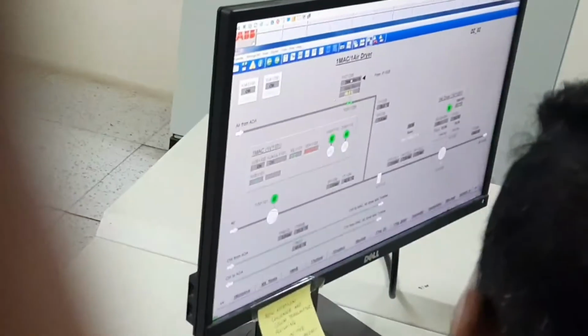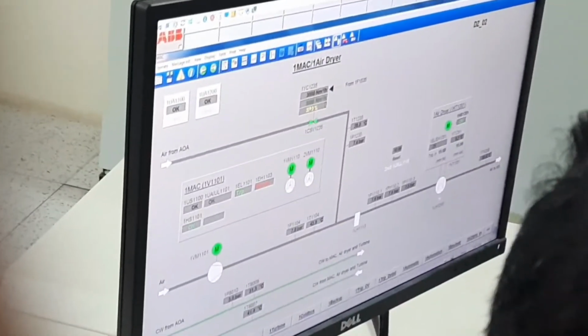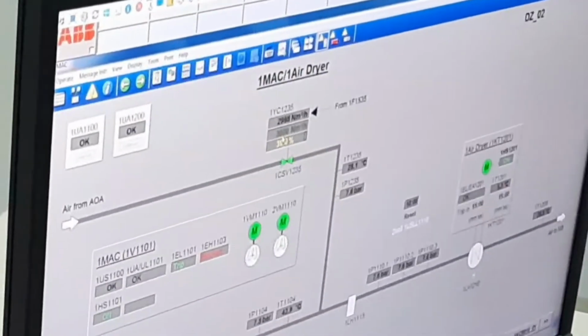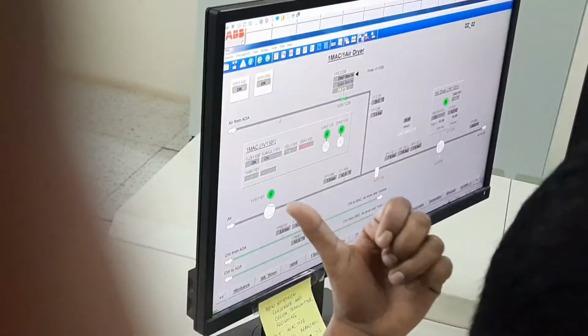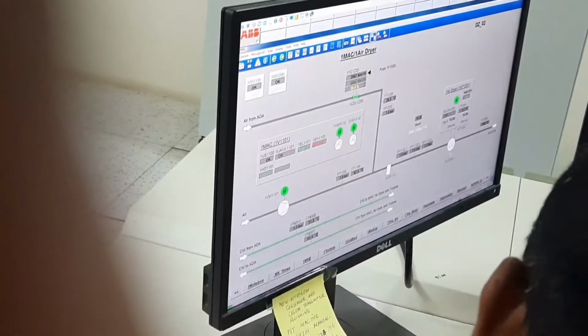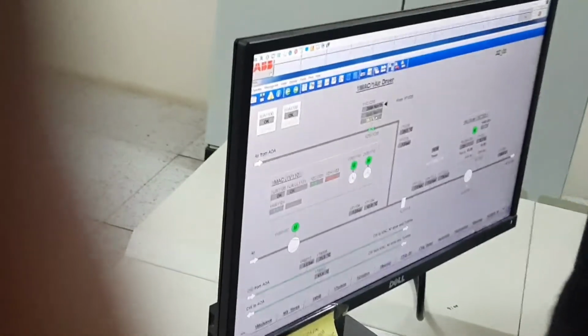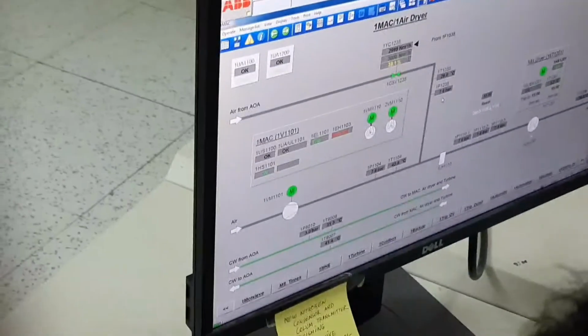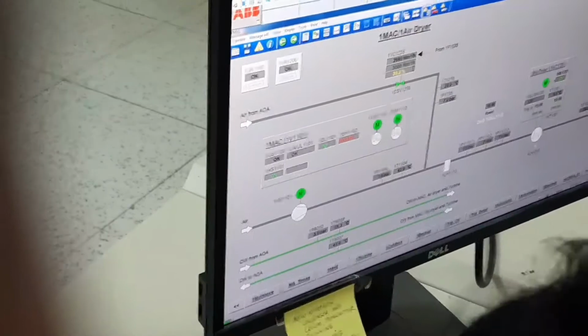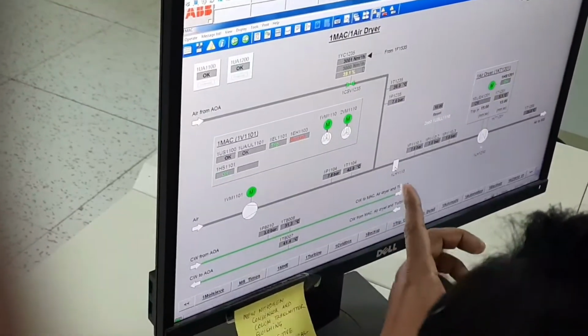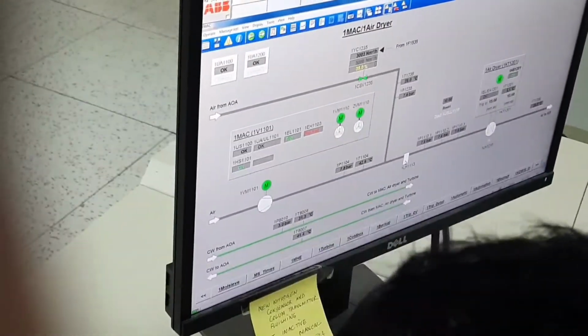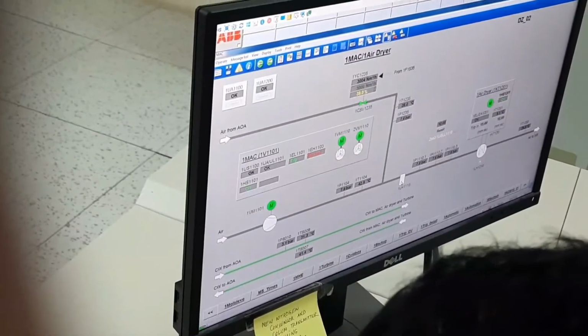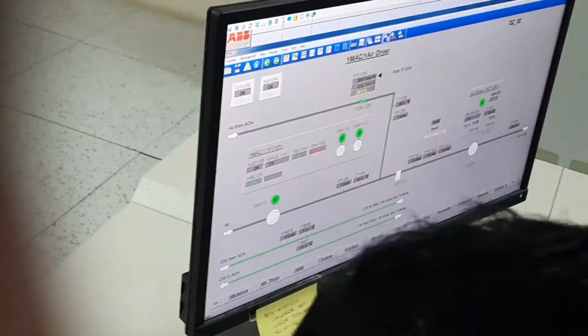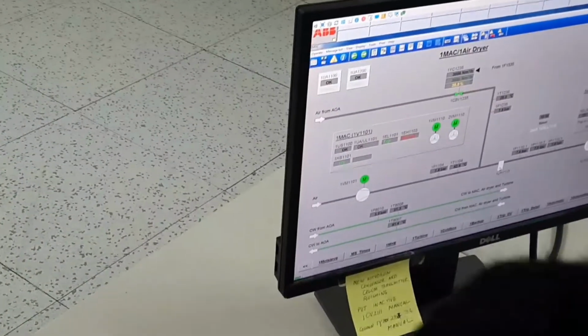Okay. So now 7.6 kg pressure. We are taking 3,000 normal meter cube air, 7.6 kg pressure, 28 degree temperature, from this air compressor. It will go through the air filter, because in the air there is also some moisture. I forgot to tell you, in the air there is moisture, and nitrogen, oxygen, CO2, CO, carbon monoxide, and some impurities also.